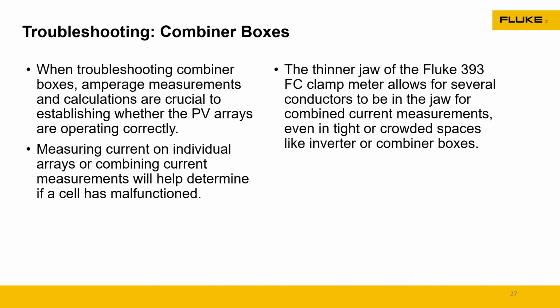If you have 10 solar panels in series and 12 of these at the combiner box, they should all generate the same voltage and current, give or take. The technician can do quick analysis there to determine if one array or line is down, or if there's a ground fault. I learned this from a company in Georgia: they trip the fuse, then measure voltage on the positive and negative coming from the arrays. If it's equal voltage, they're in good shape. You can also check positive to ground and negative to ground, expecting the same voltage as it dissipates - it's a great way to check for ground faults.